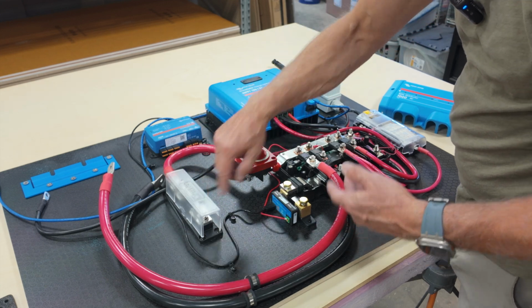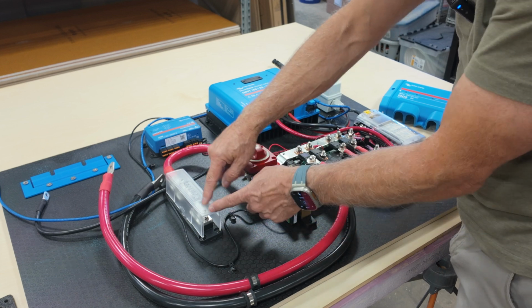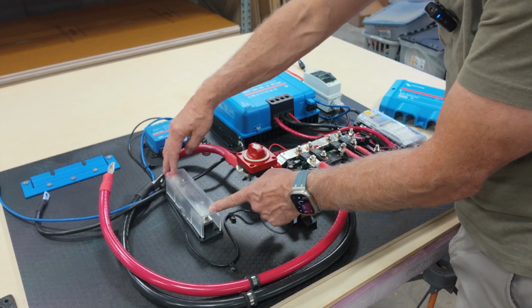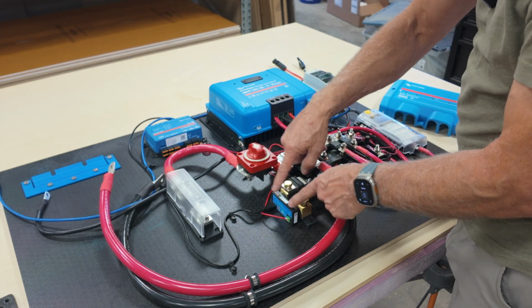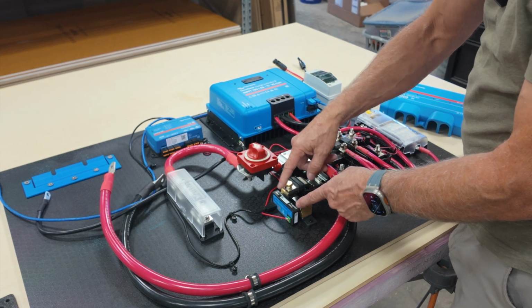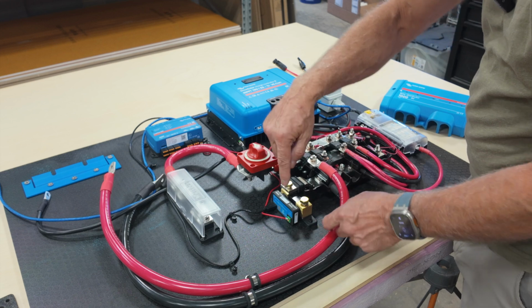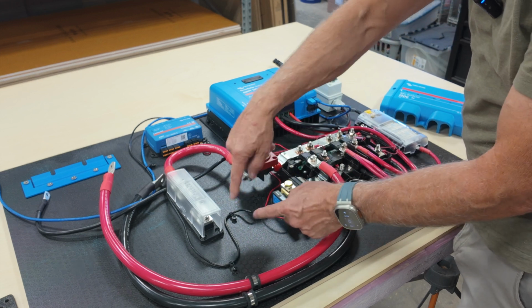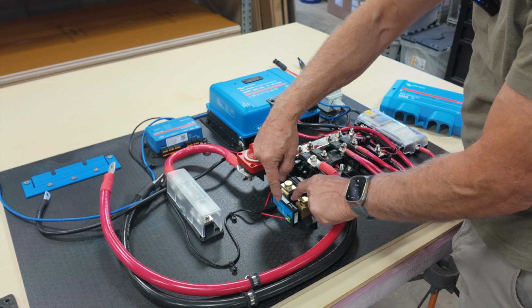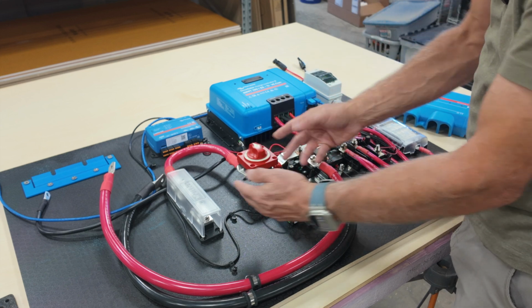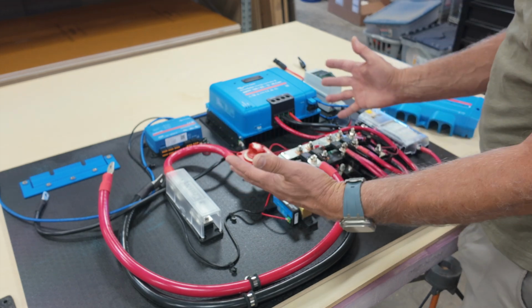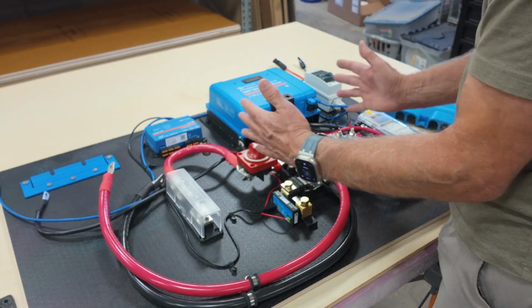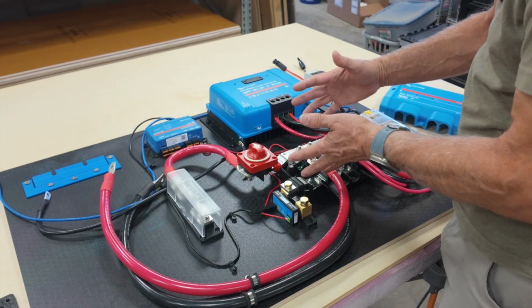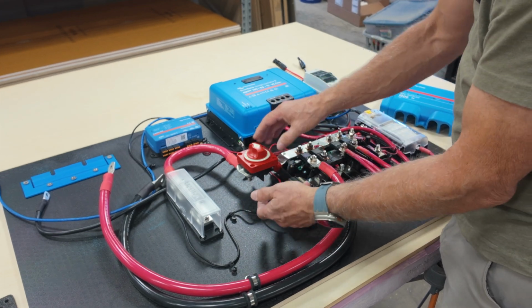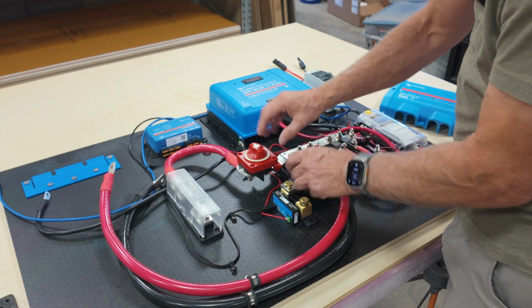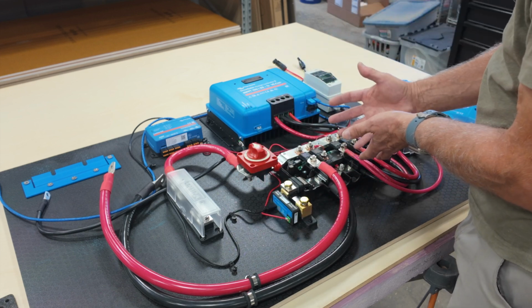We just have a cable coming from our batteries into this 400 amp ANL fuse and then into the switch. Same goes for the shunt—if you're going to have the shunt and attach it with battery cables, you'll need a 4-aught cable coming into it and another one going from the shunt into the bus bar, so you have to separate everything out. A lot of times we're working in a really tight space, and space is at a premium, so we try to keep things as compact as possible. By attaching it directly to the bus bars, we keep everything really compact.